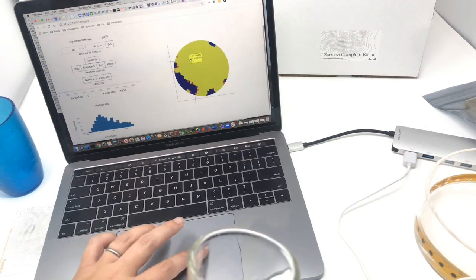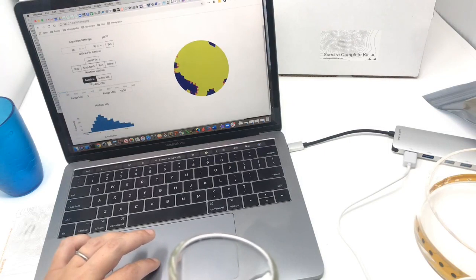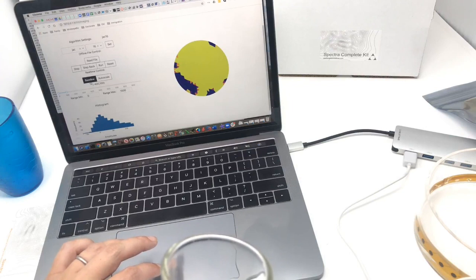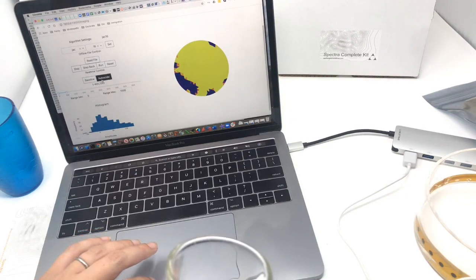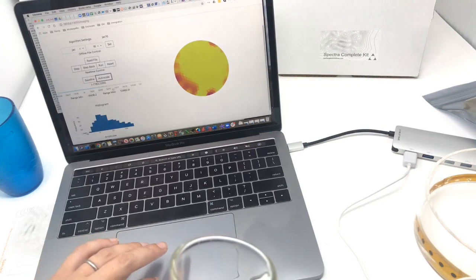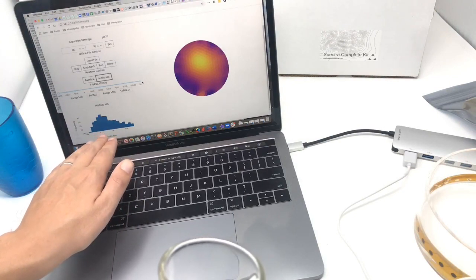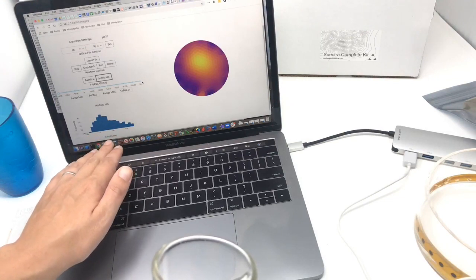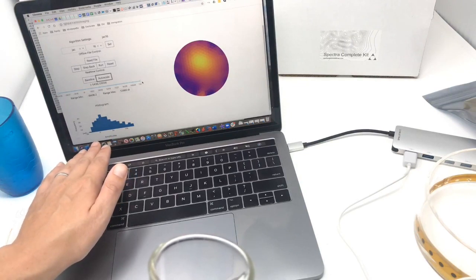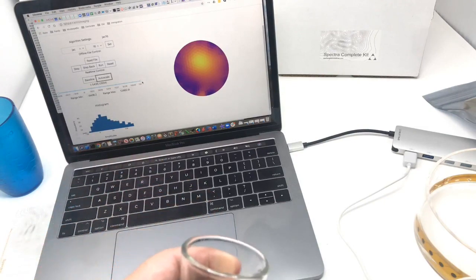In 16 electrode mode, we have a few different things on the screen. We have the ability to baseline, which will remove the background through subtracting each pixel. We've got auto scale, which picks a scale which will expand the entire range of the histogram, which is here.